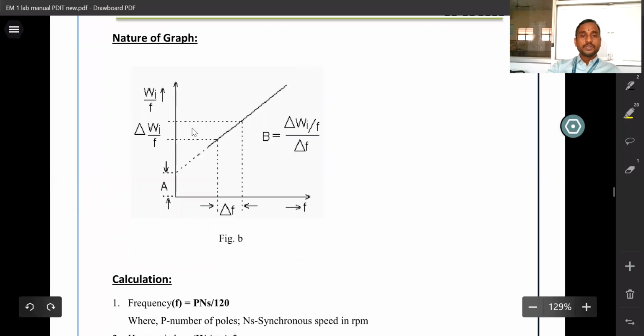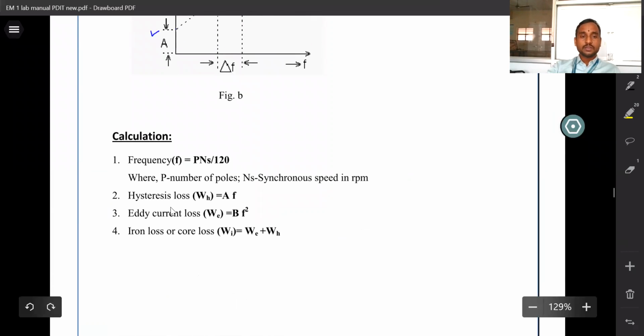After this, you need to calculate the slope, that is delta Wi by f. You take any 2 readings, and you will get delta Wi by f, and similarly you take 2 points of frequency and get delta f. The intercept is called the A part, and we need to find the B part. B is equal to delta Wi by f divided by delta f. Whatever the distance from here to here, that is delta Wi by f. Write this value of delta Wi by f, divided by the value of delta f. So you will get the A value as well as the B value. Once you know the A value and B value, you can calculate the hysteresis and eddy current loss.